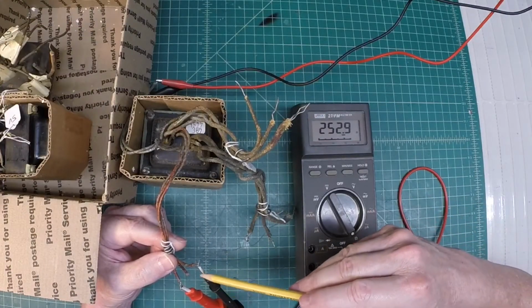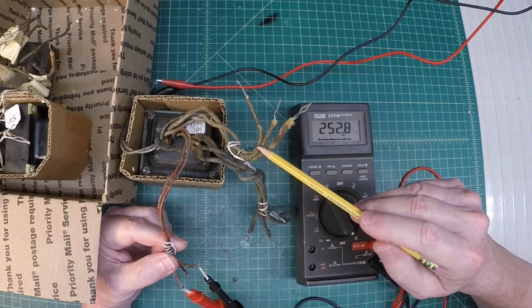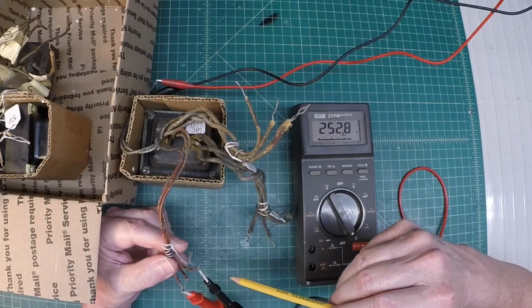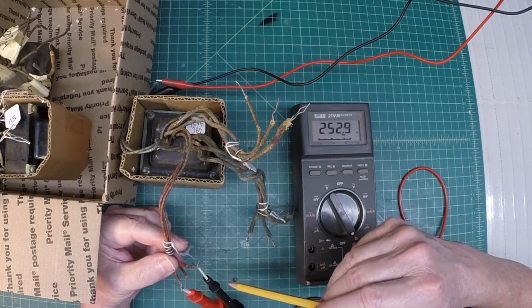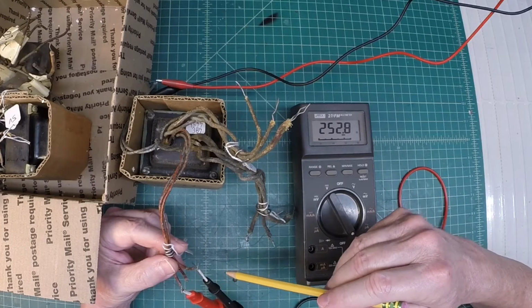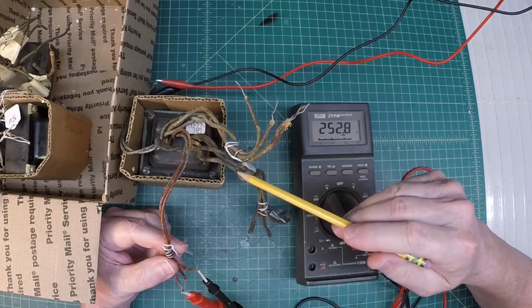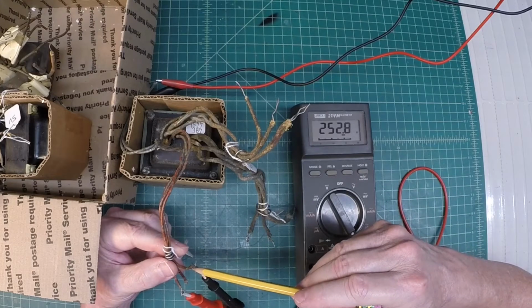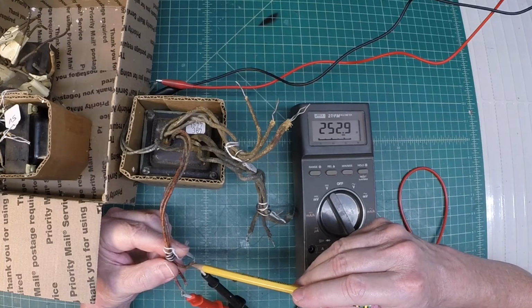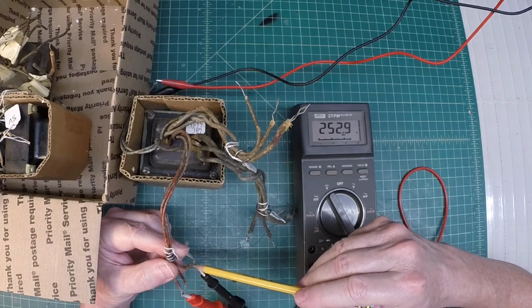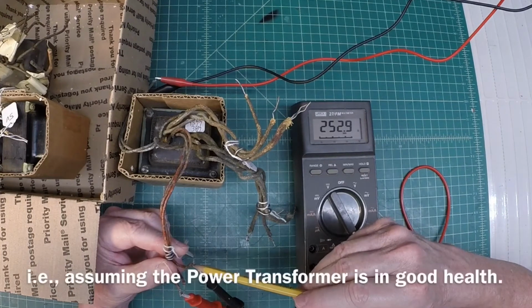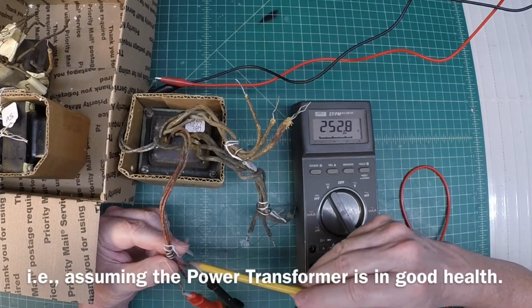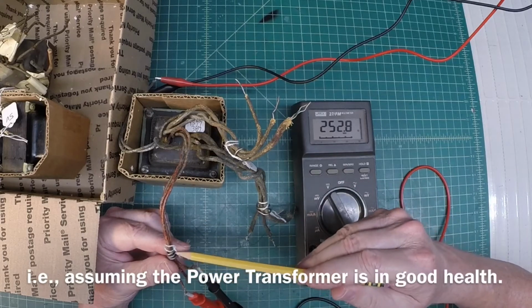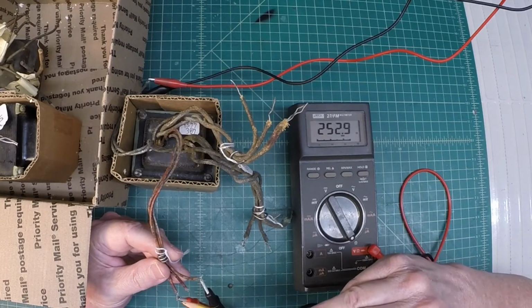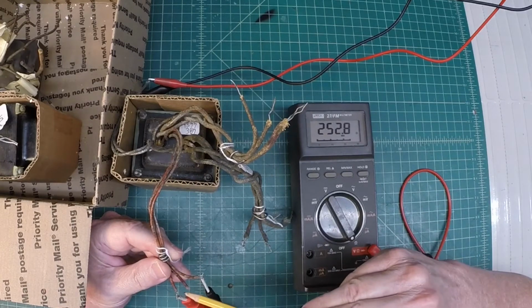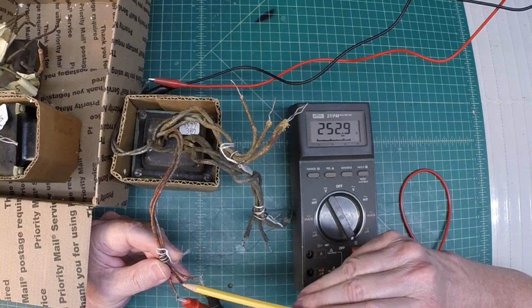You folks have seen me and many others test power transformers and easily identify the leads. I never really thought about it this way, but Mr. Duguid keeps it simple: if you're testing a power transformer like this, your high voltage windings should always be the ones with the highest amount of DC resistance. Going lead to lead, I already have these called out and separated. This is my high voltage winding, with the center being the center tap.